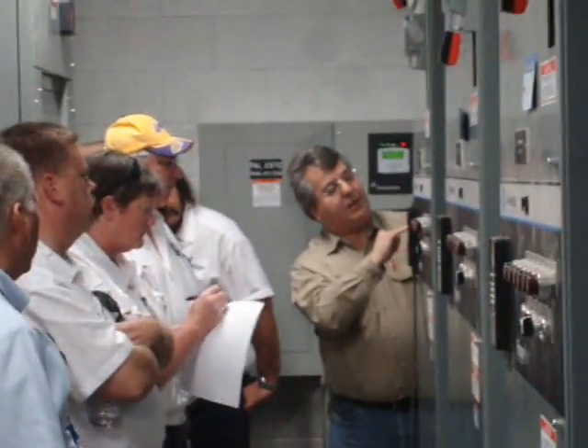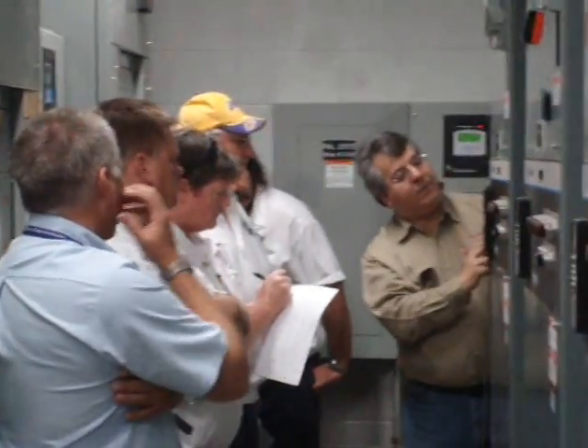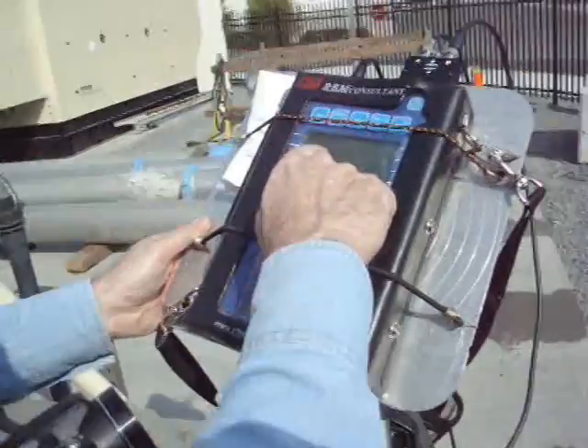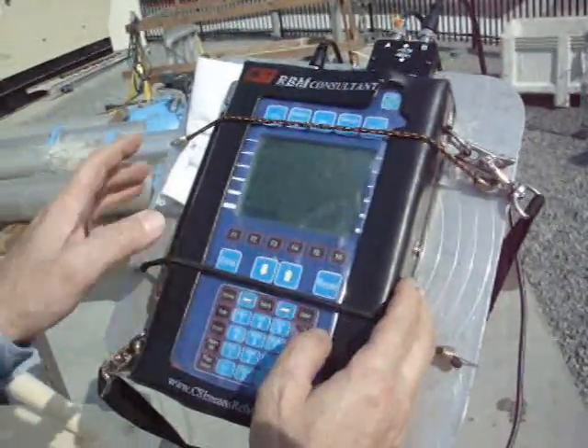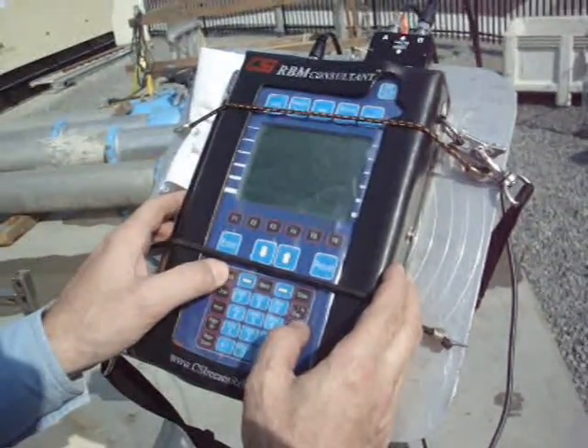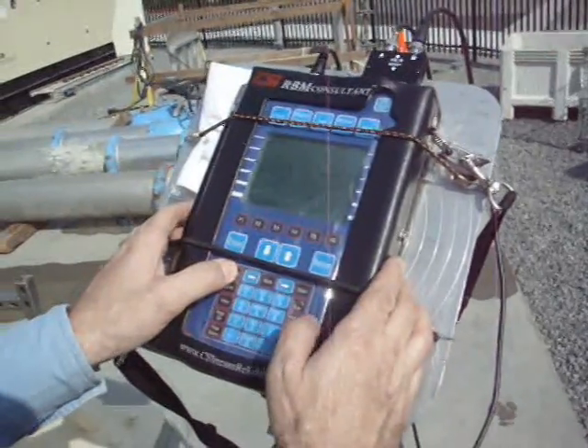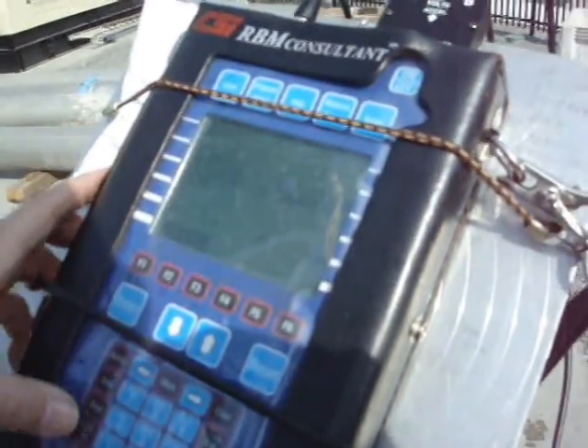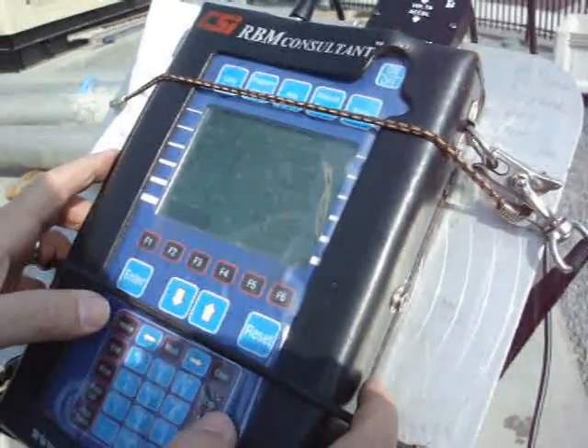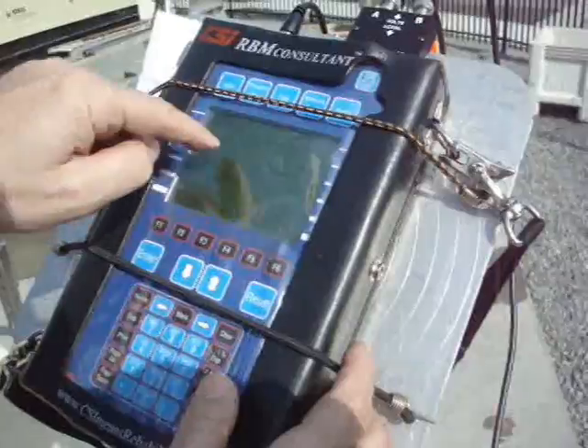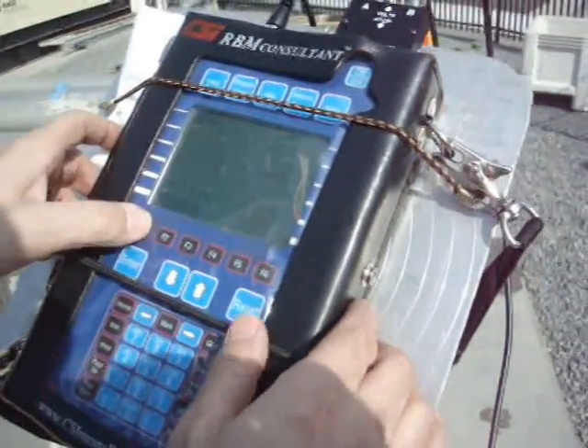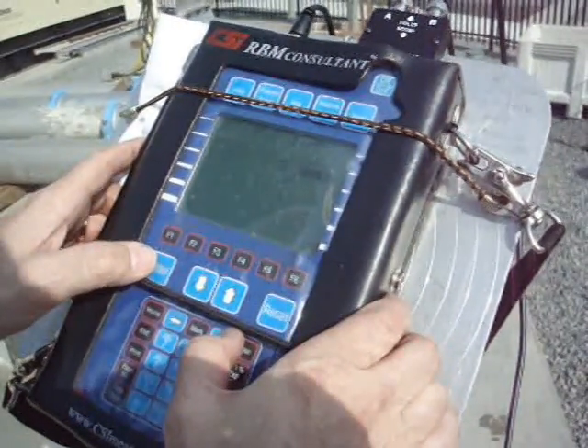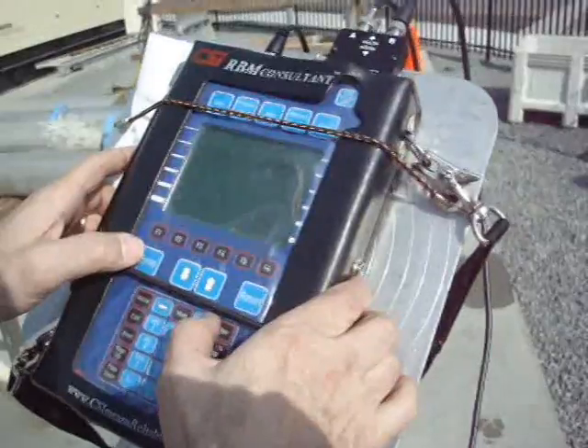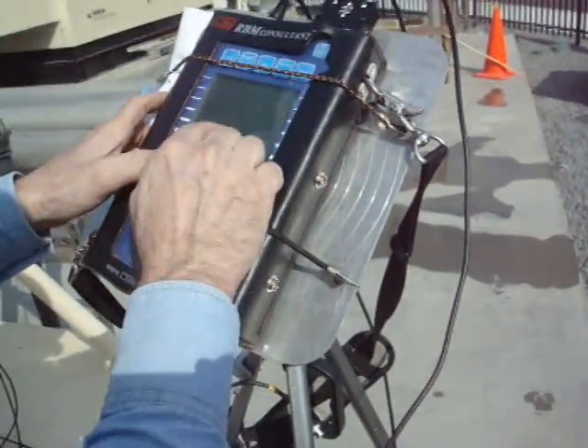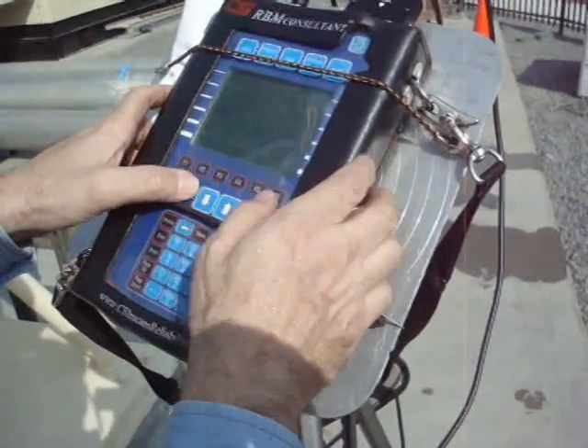Notice that when I select the basic and then I hit the enter key again. A critical part of the commissioning and startup is verification of the vibration of the pumps. We have Rush Allen from Rush Allen Engineering here to do a complete breakdown and analysis of all 4 pumps. And he predicts, using this equipment here, what frequency the pumps vibrate the most at, what hertz, and then through this process you can selectively omit certain frequencies in a VFD drive so that the pump is guaranteed to operate well within its parameters.